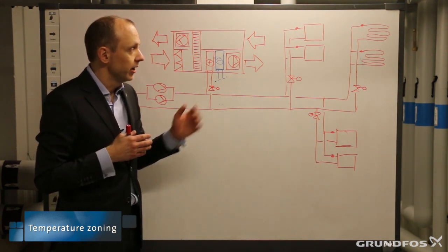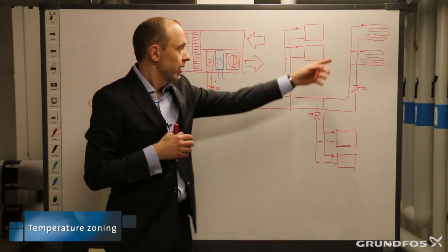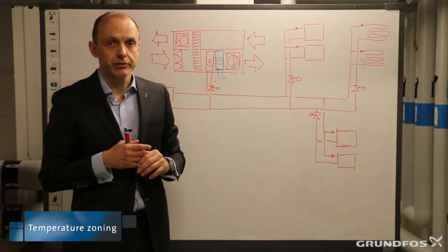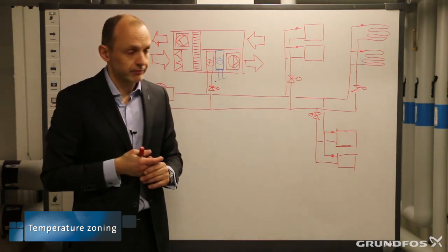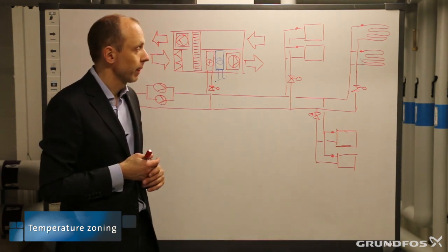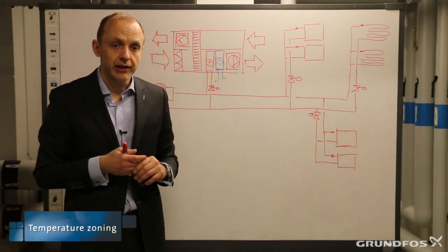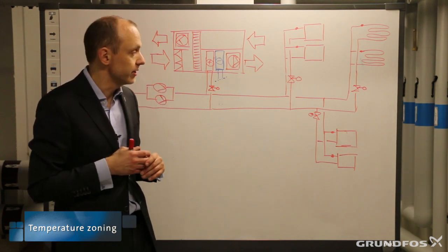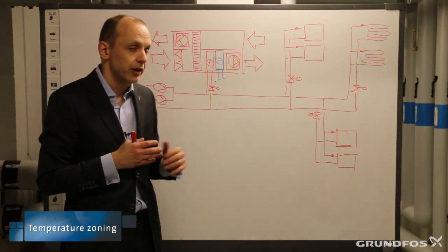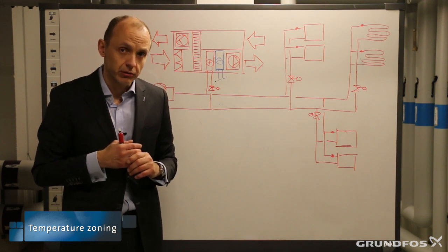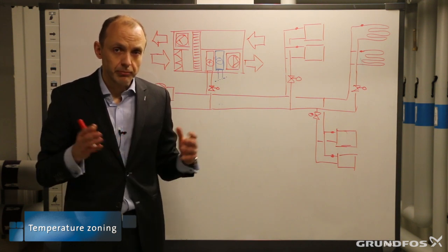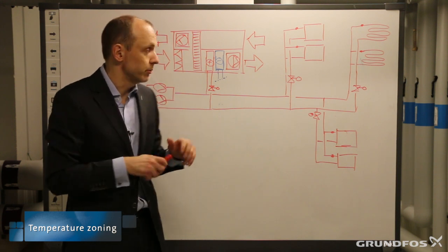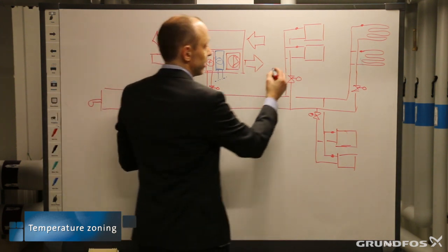Normally radiators, floor heating, and air handlers need different temperatures. So how do we do that? A very simple and well-known way to achieve this is to introduce the mixing loop, and with the mixing loop you can actually adapt the flow temperatures.